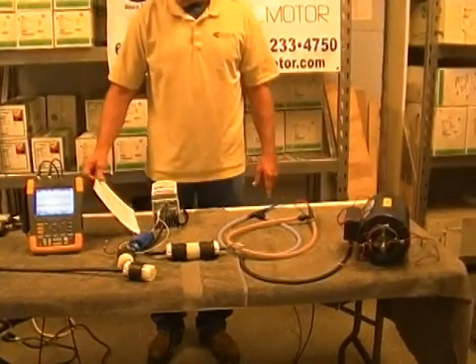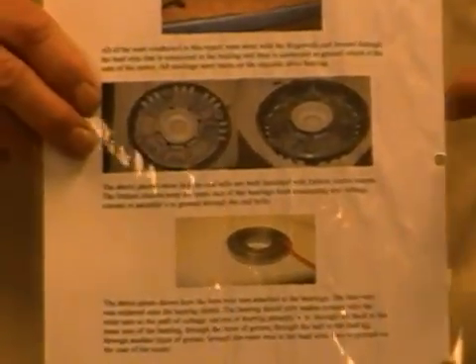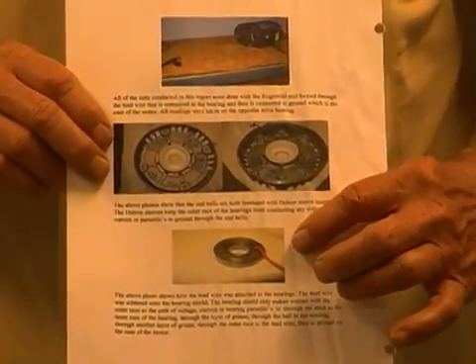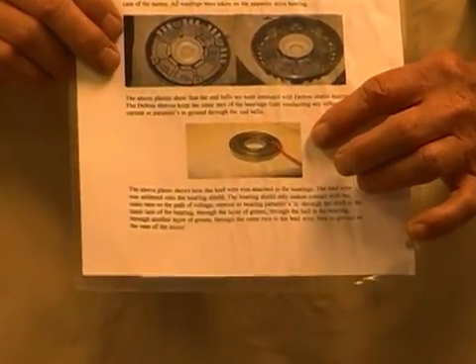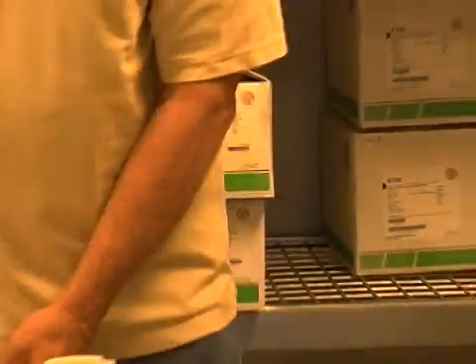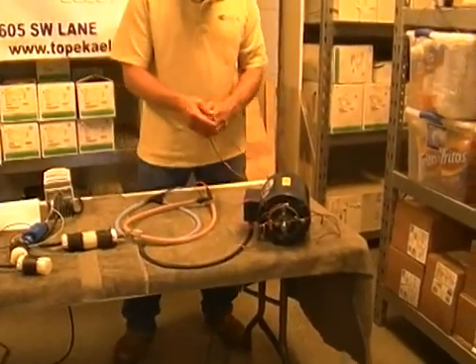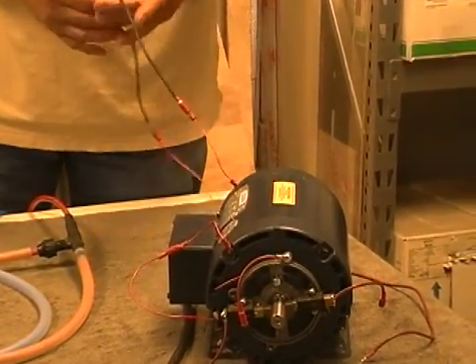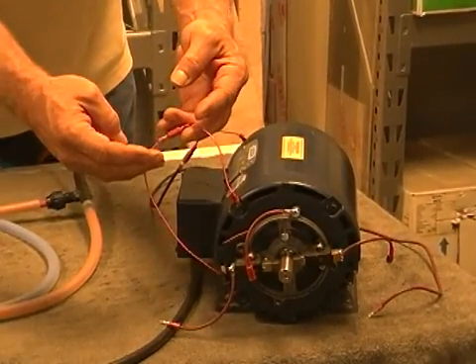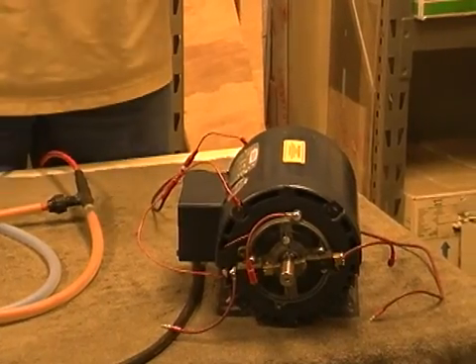Our little motor that we have here for testing has been heavily modified. As you can see in the picture, we disassembled the motor, bored the end bells, and inserted Delrin bushings into them, then remachined them back to a bearing fit. We then soldered a wire to the outer race on both bearings so we can measure high frequency current that passes through the bearings, as well as get voltage readings from the outer race to ground. By putting the Delrin bushing in, we are able to totally isolate the bearings from ground so we can get all kinds of readings.